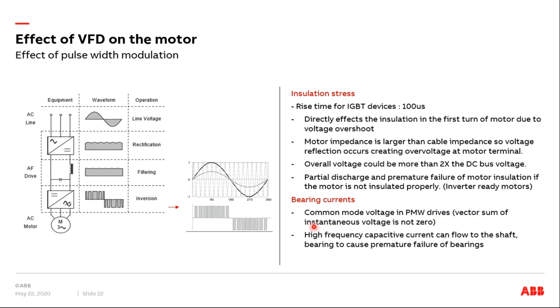Because it's switching at 4 to 8 kilohertz, you have this capacitive effect between the stator and the rotor, which creates a very high frequency signal flowing through your capacitor. So you have a current flowing from the stator to the rotor, through the shaft and through the bearing. This would create a premature failure of the bearing. So these are the two effects for the motor.